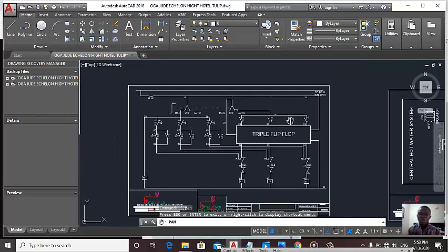Once the pressure reaches a certain level, the pressure switch will cut off that particular pump when it's not on automatic. So you need a pressure switch to cut off, to act as a switch on automatic. Once you reach a certain pressure where there's no usage, maybe nobody is using the water at that time, it will cut off the pump. Then when it cuts off the pump, the flip-flop relay will reset itself, waiting for another command for another pump to come in.